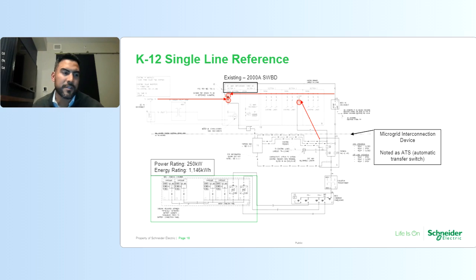As I mentioned earlier, these energy storage systems are readily commercialized, and the way consultants and integrators are disconnecting from the grid is they're assembling solutions either with a protective relay and contactor or some type of unique relay system to disconnect from the grid to enable battery resiliency. And what we're finding is, in order to offer the client maximum potential from the energy storage system, in addition to all those grid connected use cases I highlighted earlier, resiliency is becoming an important piece to getting approval for these facilities. So here they want to use the energy storage system not only for the energy optimization piece, but they also wanted to enable that energy storage system for backup power. And if you can see to the left, they have on the load side some emergency panel that, in the event of an outage, this energy storage system will provide emergency power to.